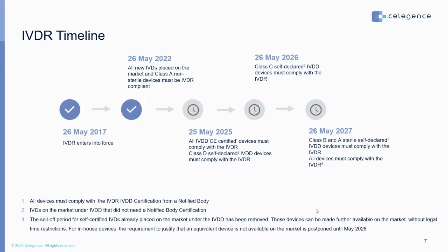All the IVDs on the market that did not require certification under IVDD must be checked again to see if the classification has been changed, and we must reevaluate if under the current IVDR guidelines they do need to be certified by a notified body. The regulations have said that the sell-off period for self-certified IVDs that are already on the market is removed. These devices can be made available on the market without any legal time restrictions. And for all in-house devices, the requirement to justify that an equivalent device is not available in the market is postponed until May 2028.